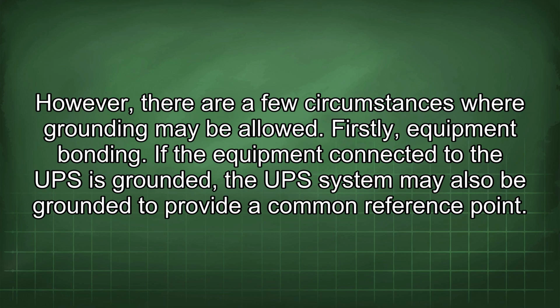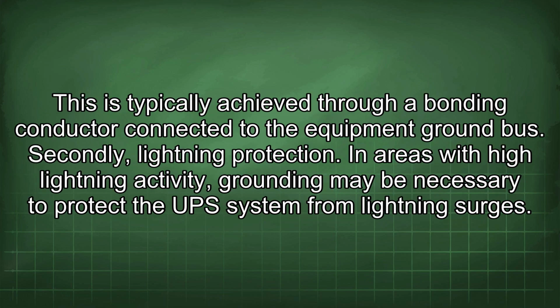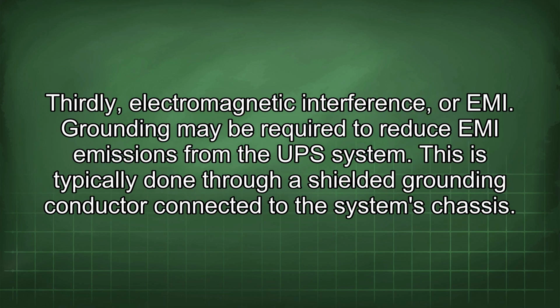Firstly, equipment bonding. If the equipment connected to the UPS is grounded, the UPS system may also be grounded to provide a common reference point. This is typically achieved through a bonding conductor connected to the equipment ground bus. Secondly, lightning protection. In areas with high lightning activity, grounding may be necessary to protect the UPS system from lightning surges. Thirdly, electromagnetic interference, or EMI. Grounding may be required to reduce EMI emissions from the UPS system. This is typically done through a shielded grounding conductor connected to the system's chassis.